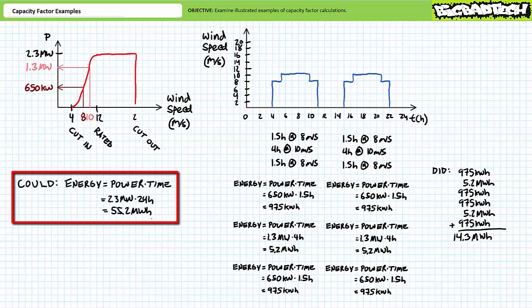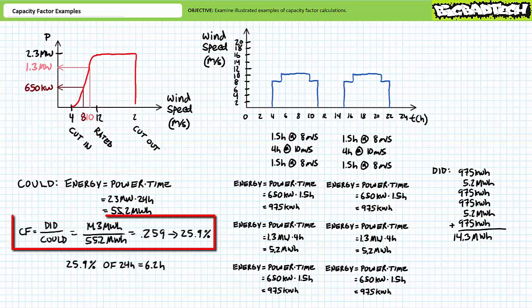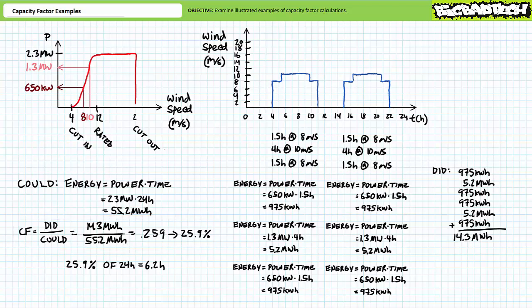Now let's determine how much energy this turbine could produce. Theoretically, this turbine could run at full capacity 24 hours a day. Energy is power times time — 2.3 megawatts expressed for 24 hours yields a theoretical maximum energy output of 55.2 megawatt hours every day. Capacity factor is did over could: 14.3 megawatt hours over 55.2 megawatt hours demonstrates the turbine has a capacity factor of roughly 25.9%, meaning it produces an equivalent amount of energy as if it ran at full capacity — 2.3 megawatts — for 25.9% of a day, roughly 6.2 hours. Each day the turbine produces enough energy as if this were true.